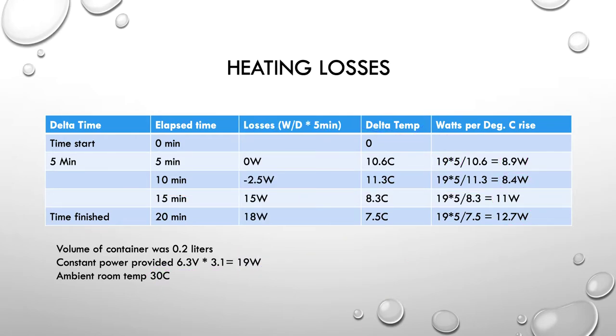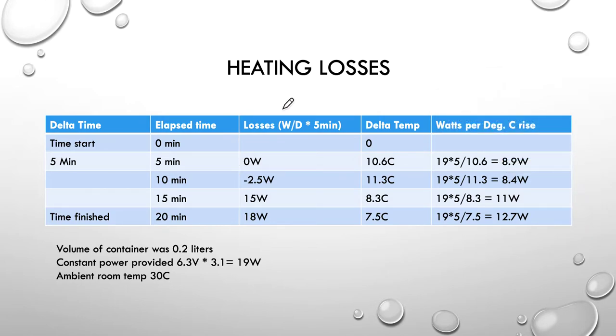So, the heating losses. I've done another little calc here and added this column now. We've still got our delta temperature. Our watts per degree rise and all I've done is said the watts divided by the delta temperature multiplied by 5 kind of gives you the losses, gives you some idea what the losses are. Obviously, there are no losses when you start.